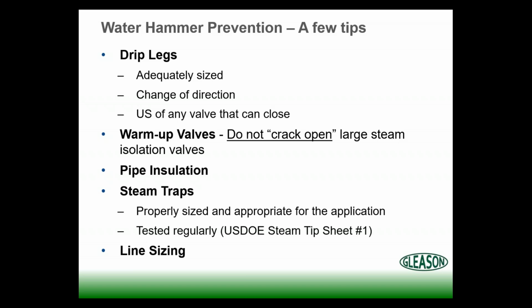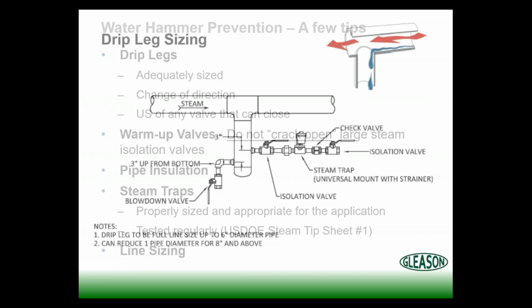The DOE has a steam tip sheet, number 1, entitled Inspect and Repair Steam Traps. The Steam Best Practices Committee for the U.S. DOE recommends testing traps for what they consider to be medium pressure steam, which is from 30 to 150 PSI, monthly to quarterly.